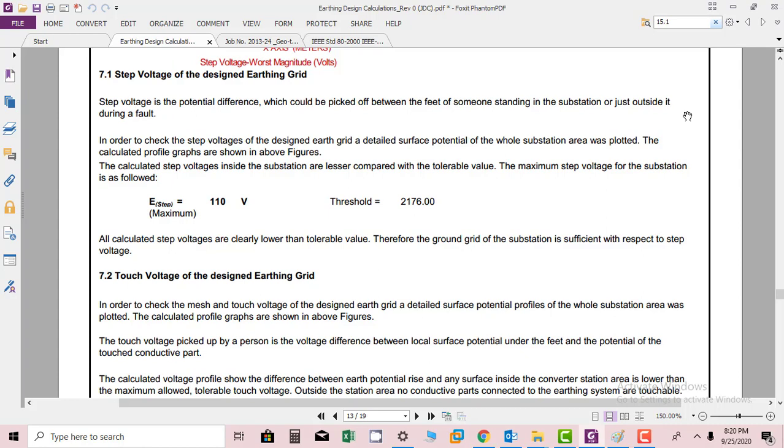The calculated step voltage inside the substations are lesser compared with the tolerable value. The maximum step voltage for the substation is as follows: we have seen from the previous graph the maximum step potential is 110 volts, whereas the threshold voltage is 2176 volts, which is almost 2.176 kV.